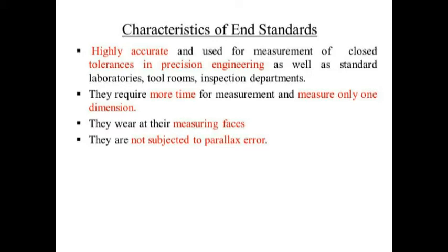The accuracy of both the standards is affected by temperature change, and both are calibrated at around 19 to 21 degrees centigrade. It is also necessary to take utmost care in their manufacturing to ensure that the change of shape with time and secular change is reduced to negligible.